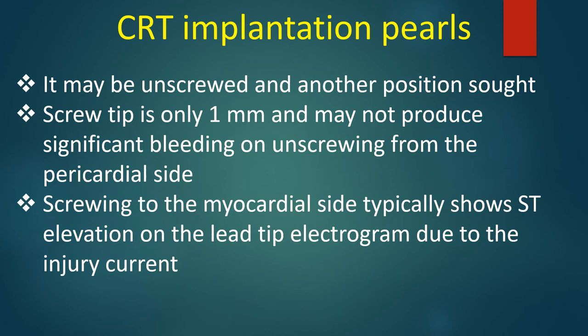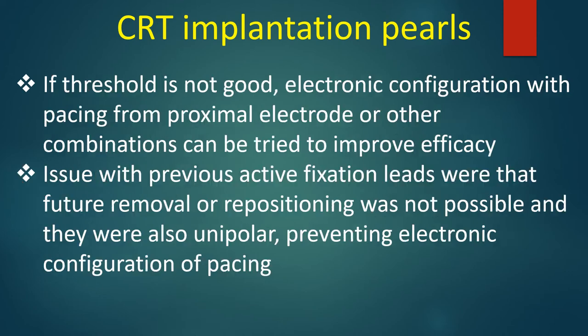Screwing to the myocardial side typically shows ST elevation on the lead tip electrogram due to the injury current. If the threshold is not good, electrode configuration with pacing from the proximal electrode or other combinations can be tried to improve efficacy.